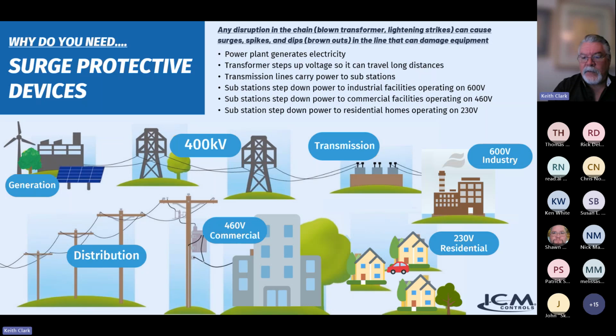And then it'll go through another substation where it comes to your residential areas. It comes in as 230 volt, but it goes into a residential panel, and they break those apart into 115 and 115. So it goes into the panel. They refer to it as split phase. There are two independent bus bars that are each 115 volt. And so for your lights and your power outlets and so on, they'll just use one breaker that contacts one of those bus bars.